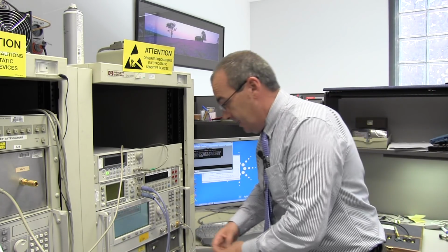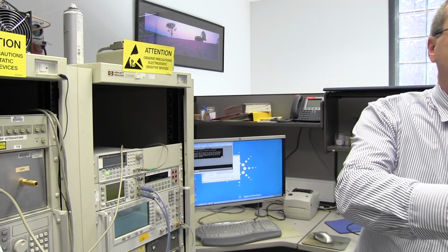The methods, there always has to be a repeatable method. There always has to be a documented method. There always has to be a quality system that backs it up. There's no point in a box coming in and me deciding I know how to do it and just plugging it in, calibrating it and saying, yeah, here's your box. All right. You've got to have that documentation behind it because that's the basis of your quality system. Part of your quality system is you have to keep a record of what you do. You have to keep a record of the calibration report and the certificate.